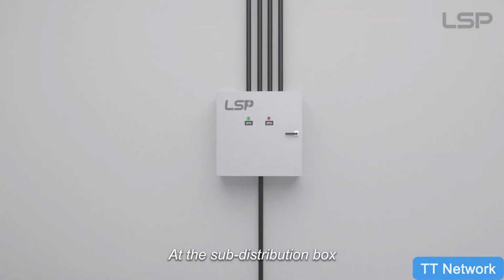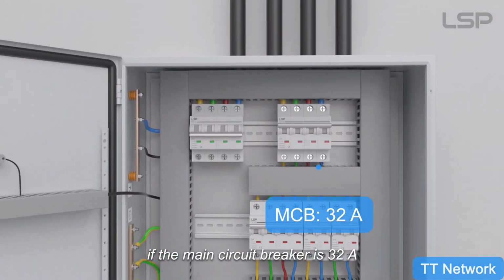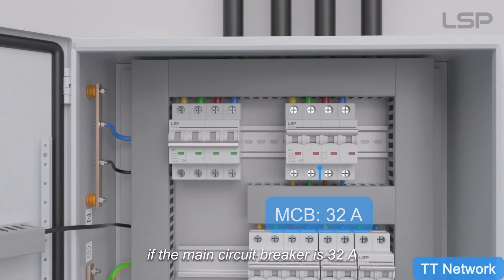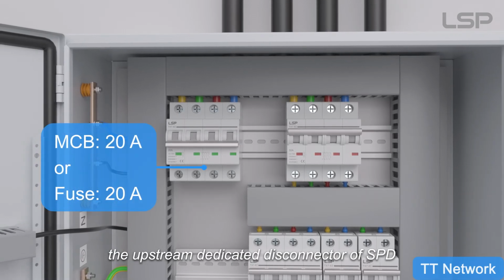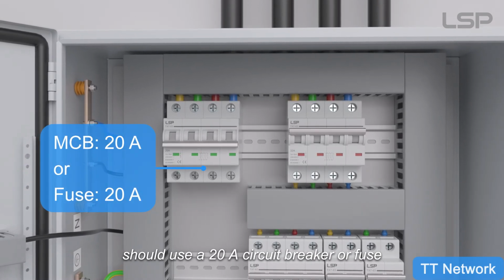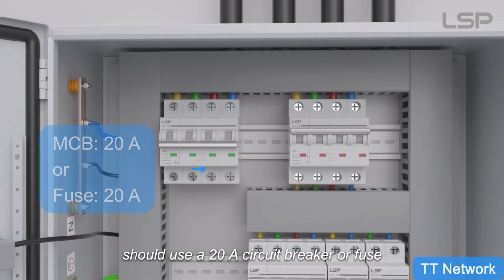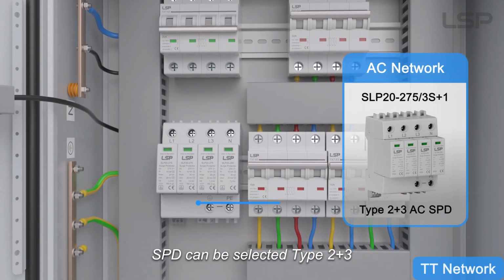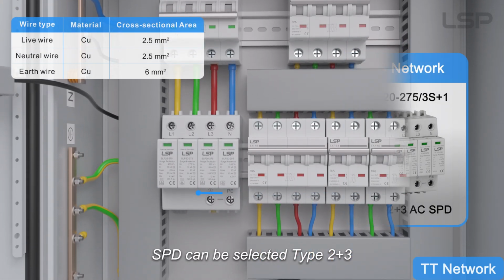At the sub-distribution box, if the main circuit breaker is 32 amps, the upstream dedicated disconnector of SPD should use a 20 amp circuit breaker or fuse. SPD can be selected type 2 plus 3.